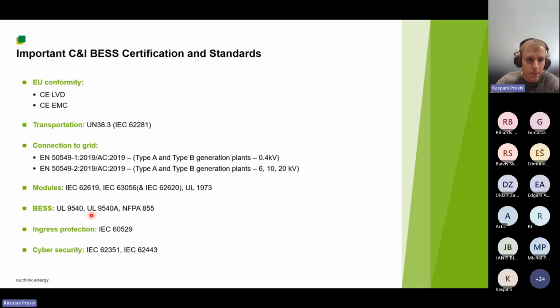But I would like to point out some safety standards that are important if we talk from the safety perspective. And this is UL 9540 and UL 9540A, which basically are test results for these battery systems regarding their flammability and their thermal runaway. These tests, these standards basically provide a test result which shows if these batteries will have thermal runaways, if they will cause fire and how severe it can be. So these are important things to have for your systems. And of course, we have this fire safety standard NFPA 855, which is also important.